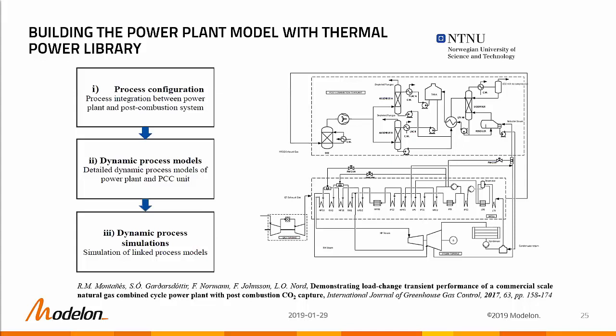The second step was to develop dynamic process models of both the power plant and the capture unit, using the Thermal Power library from Modelon. For the power plant, we used several components from the library to represent the actual equipment in the power plant design, for example high pressure superheaters, reheaters, intermediate pressure superheaters, evaporators, economizers, drums, steam turbine expansion components, and condenser, as well as pumps, valves, and the controllers and control blocks representing the control structure of the power plant.